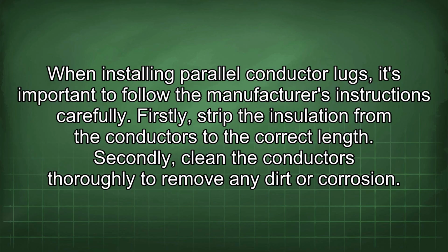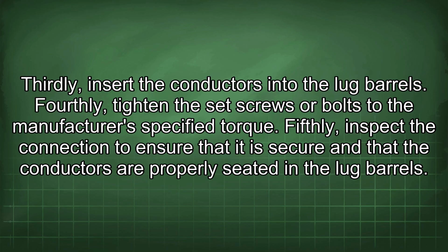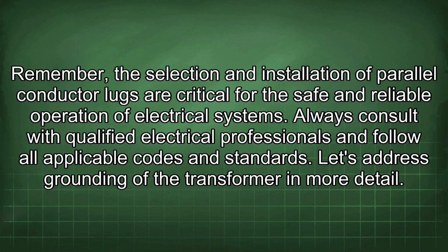When installing parallel conductor lugs, it's important to follow the manufacturer's instructions carefully. Firstly, strip the insulation from the conductors to the correct length. Secondly, clean the conductors thoroughly to remove any dirt or corrosion. Thirdly, insert the conductors into the lug barrels. Fourthly, tighten the set screws or bolts to the manufacturer's specified torque. Fifthly, inspect the connection to ensure that it is secure and that the conductors are properly seated in the lug barrels. Remember, the selection and installation of parallel conductor lugs are critical for the safe and reliable operation of electrical systems. Always consult with qualified electrical professionals and follow all applicable codes and standards.